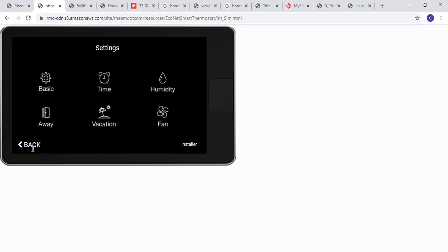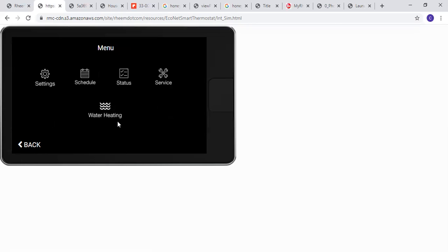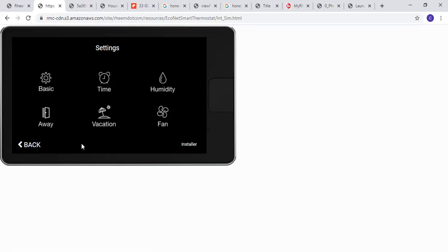Now, you also have a feature which this demo doesn't show us. But if we go into settings normally, we'll have an option down here to say checkout or test mode. So we can go in here and say if we're having a 98V or 97V, we can go into test mode. We can click that. We can physically from the thermostat here, instead of doing dip switches, set it in high heat, 100% capacity. Then we can also go in and set it at low heat, and then we can set our pressures and check our pressures that way.